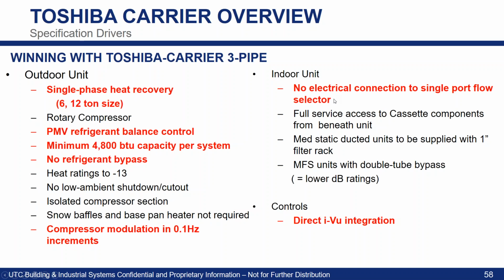Also with the single port flow selectors, which is important, and it's a nice feature in that they're completely 100% sealed, so no worry on condensate there. They do not have a condensate line, while the larger flow selectors, that being 4 and 6 port, do require a condensate line.